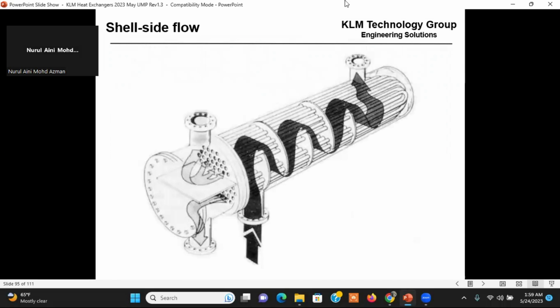Well, if I have a fouling service and I'm going here and under and up and down and up and down, what happens right here? Okay, so I come in here, I go under, I go up. I have a dead zone right there, and I'm going to fill that whole section up with trash. If I put just small notches under this baffle, typically I want the flow to go down, okay, for fouling service. But if I put small notches underneath these baffles, okay, that trash won't fill up and it'll come and go out.